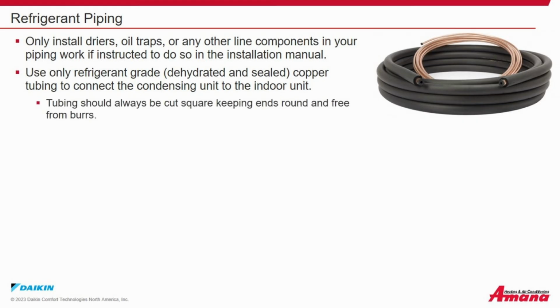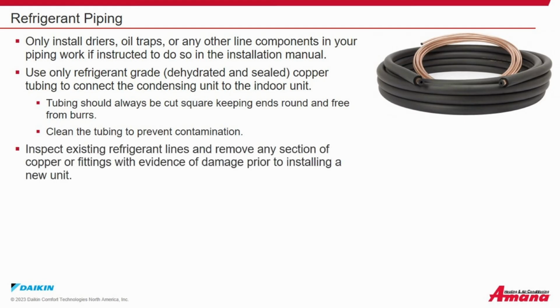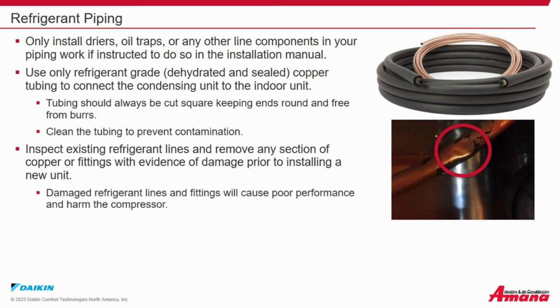Tubing should always be cut square, keeping ends round and free from burrs. Clean the tubing to prevent contamination. Inspect existing refrigerant lines and remove any section of the copper fittings with evidence of damage prior to installing a new unit. Damaged refrigerant lines and fittings will cause poor performance and harm the compressor.